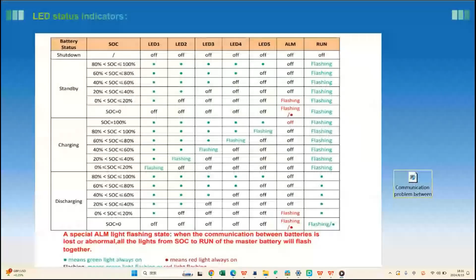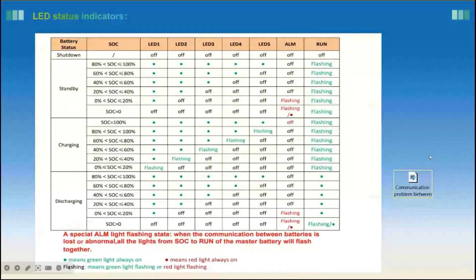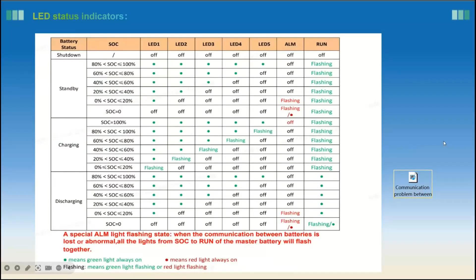In this case, how do we do the troubleshooting? We first confirm whether the battery sleep setting has been set correctly. All the dip switches should be 00, and then we need to confirm that when we set the dip switch, we powered off the battery and restarted it. And then we need to check whether the communication cable between battery and battery is the correct communication cable with 8 pins. Okay, this is just a simple problem during installation, but we need to pay attention and know how to do the troubleshooting.